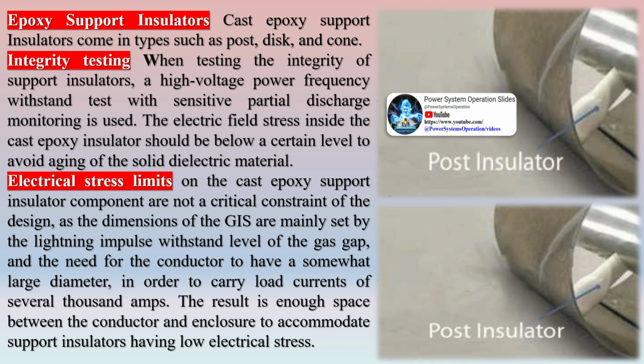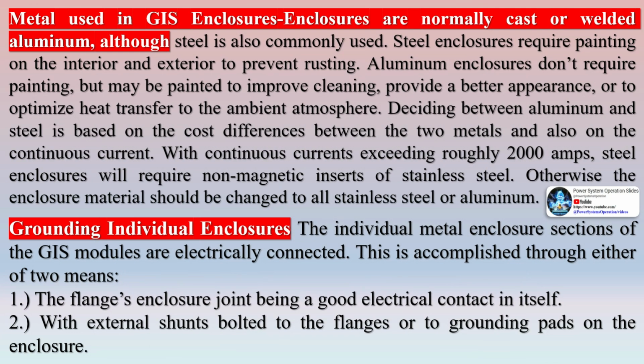Electrical stress limits on the cast epoxy support insulator component are not a critical constraint of the design, as the dimensions of the GIS are mainly set by the lightning impulse withstand level of the gas gap, and the need for the conductor to have a somewhat large diameter, in order to carry load currents of several thousand amps. The result is enough space between the conductor and enclosure to accommodate support insulators having low electrical stress.